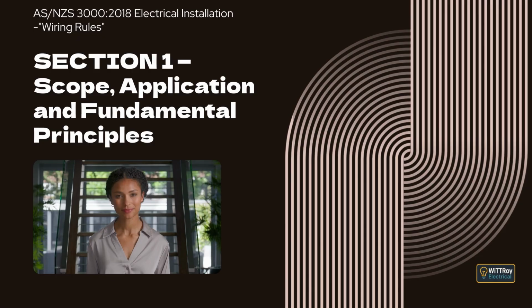Clause 1.4.103 is ripple-free DC. This applies to sinusoidal ripple voltage where the ripple content does not exceed 10% RMS. Clause 1.4.104 is safety service. A safety service is a system or component that operates during an emergency and is mainly associated with helping people evacuate a building, supporting firefighting operations, or providing fire suppression. Examples include fire detection systems, smoke control systems, evacuation systems, and emergency lifts.